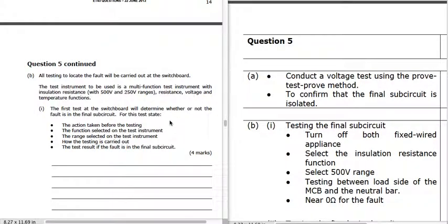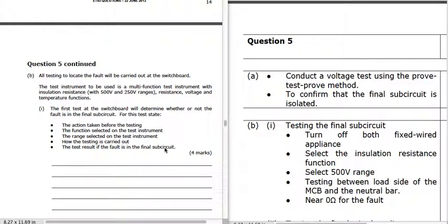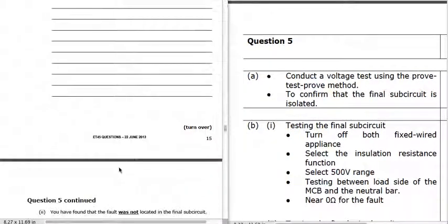We do a test at the switchboard to determine whether the fault is in the final sub-circuit. Turn off the fixed appliances because we don't want them part of the test. Use the insulation resistance function, select 500 volts, and test between the load side of the MCB and the neutral bar. If there is a fault in the system we'll get near zero ohms. If there's no fault, we'll get 1 megaohm or more. The test result, if the fault is in the final sub-circuit, will be a very low resistance near zero.